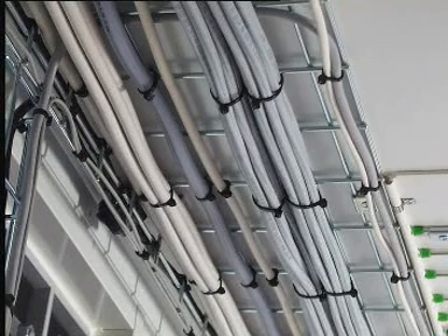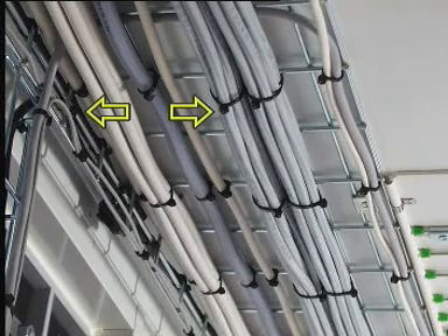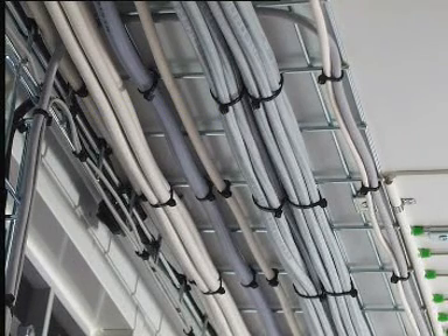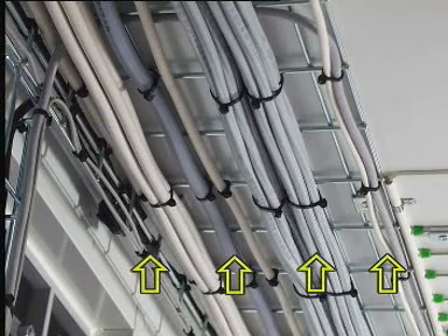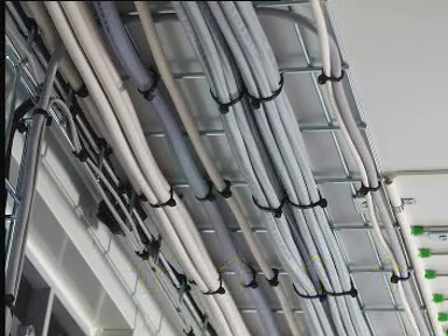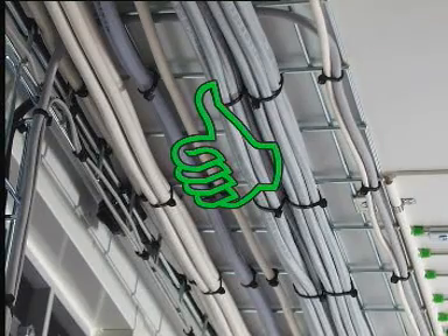As a general rule, power and signal cables should be kept to the opposite sides of a cable ladder. Cables with similar functions may be grouped together, for example, AC, alarm, DC, and PCM cables. This standard is perfectly acceptable.